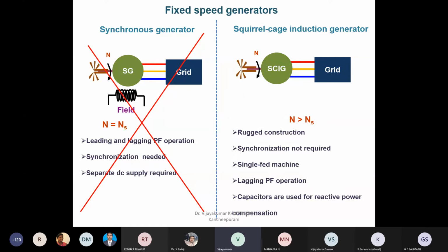In fixed speed wind turbines, we never use synchronous machines. There are three reasons for this. One is, if you want to make a synchronous machine work as a generator, we've done the experiment in our lab too. To get a 50 hertz output exactly, say for a 4-pole machine, you have to rotate it at exactly 1500 RPM. If you operate at 1505 RPM, the frequency will change, creating a lot of issues in the system. Since wind is variable, you cannot operate at exactly 1500 RPM. That's why synchronous machines are not preferred for wind turbines.